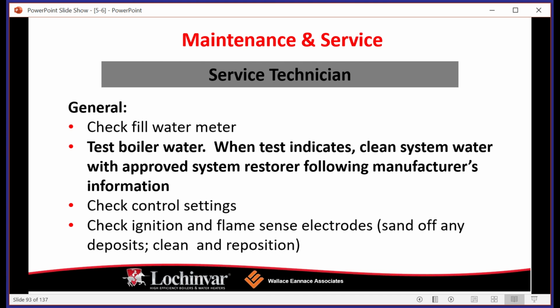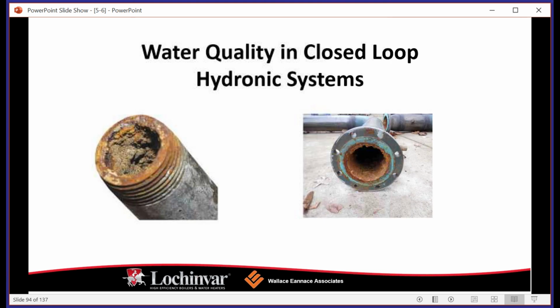And what they're going to do is they're going to come out. We're going to review your venting. We're going to make sure the pumps are set up correctly. We're going to make sure that your condensate is being handled in the proper fashion. We're going to turn the boiler on. We're going to help do the programming. And we're also going to do a combustion calibration, make sure the boiler's running in the way that it needs to, and so forth. Again, if you're a skilled contractor, this is stuff that you're comfortable with.